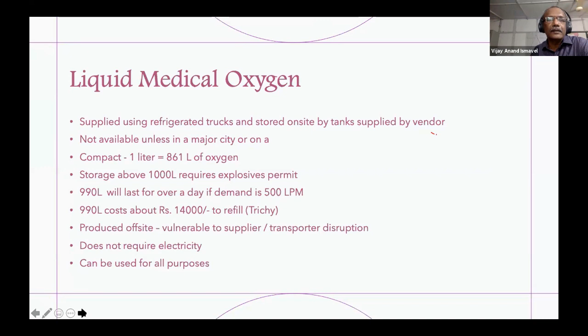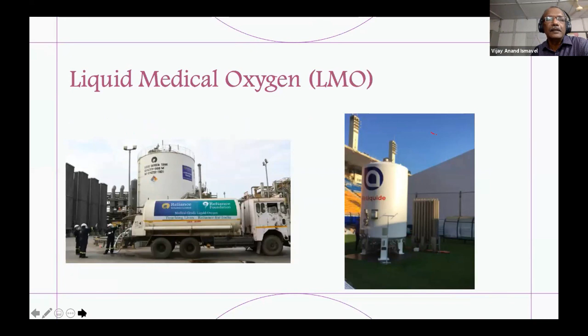And since Indian law requires an explosives permit for storing more than 1,000 liters, the usual storage capacity is 990 liters, which will last for about a day if the demand is 500 liters per minute. So I've written about the cost there. Again, it does not require electricity and can be used for all purposes. So that is a liquid medical oxygen manufacturing and storage facility.